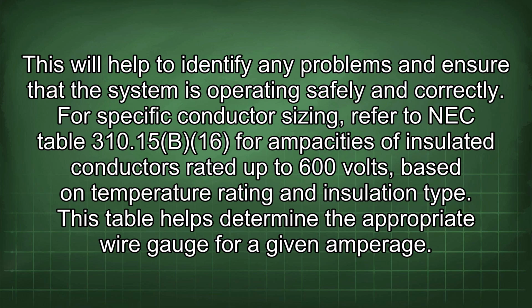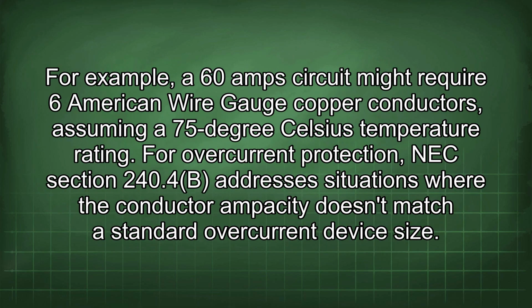For specific conductor sizing, refer to NEC Table 310.15(B)(16) for ampacities of insulated conductors rated up to 600 volts based on temperature rating and insulation type. This table helps determine the appropriate wire gauge for a given amperage. For example, a 60-amp circuit might require 6 American wire gauge copper conductors, assuming a 75°C temperature rating.